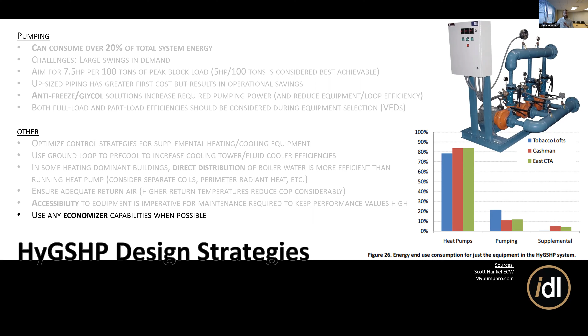Then ensure adequate return air. If you're installing a heat pump system, the biggest driver of its load is trying to heat up the air you're distributing through the house. This might be a good situation for an ERV or HRV, a heat recovery ventilator, so you can reduce the load on those indoor coils and require less pumping energy. During the summertime, make sure you're employing an economizer, so any free cooling we can get from the outdoor air, like early in the morning, basically the idea of opening up windows to cool down surfaces. An economizer is a more automated way of doing that through your HVAC system, so instead of asking your heat pump to cool that air down, you rely on outdoor air directly whenever possible.